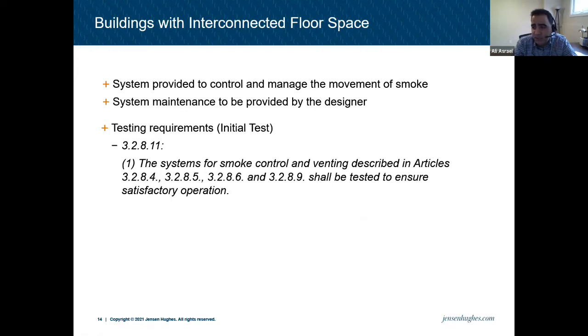The system maintenance needs to be provided for these types of systems by the designer of the system. We can talk about it later when we get to fire code requirements. And there is, again, an initial test requirement in the building code. 3.2.8.11 says the systems for smoke control and venting described in articles 3.2.8.4, 3.2.8.5, 6, and 9 shall be tested to ensure satisfactory operation. Again, you see that this is the building code asking for the test. We need that test before the occupancy if there is such a smoke control system in the building.